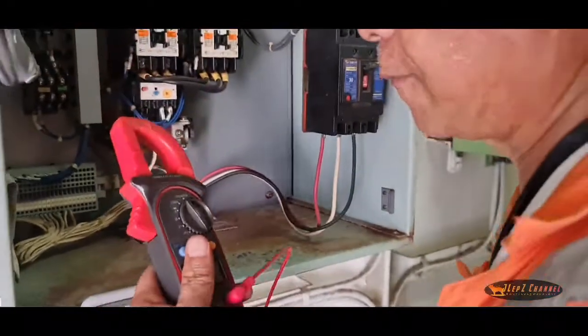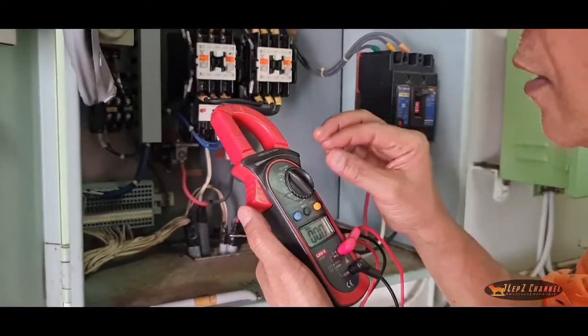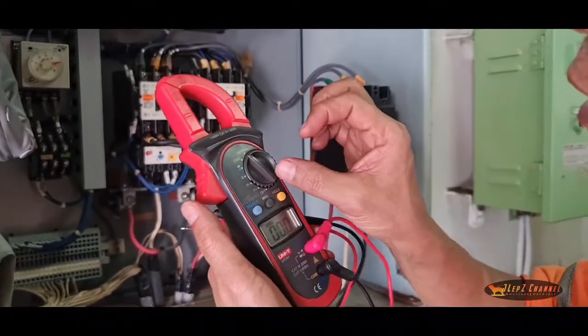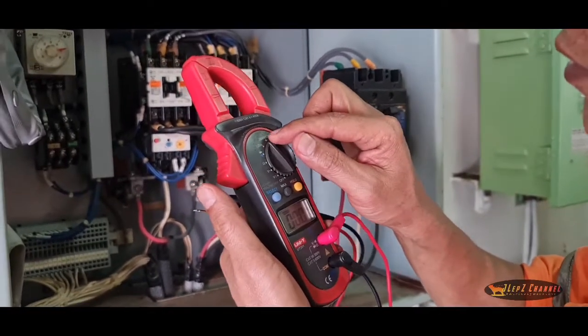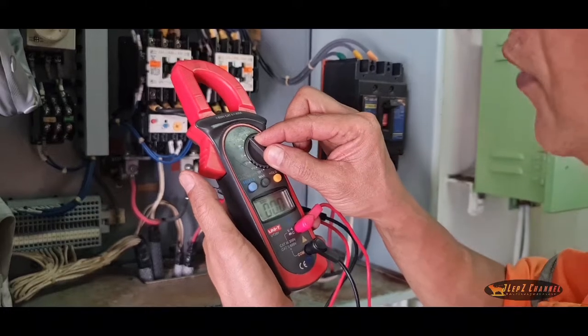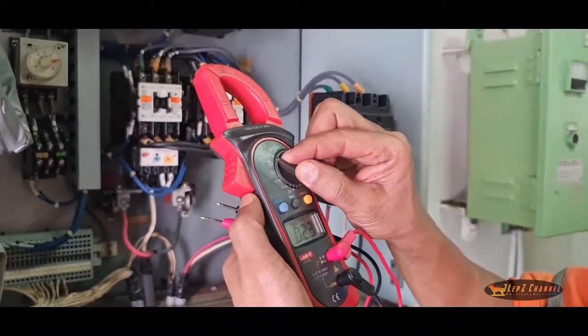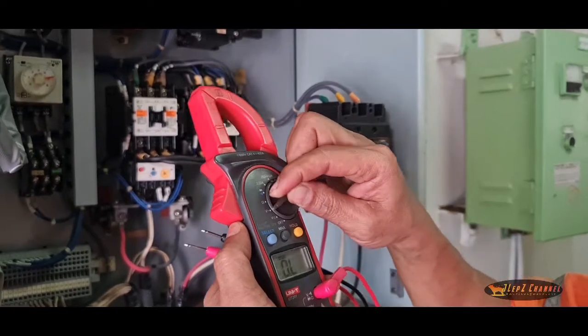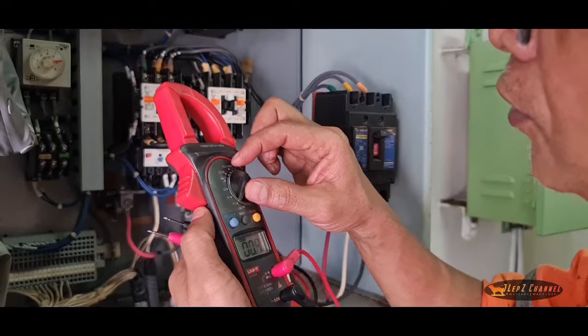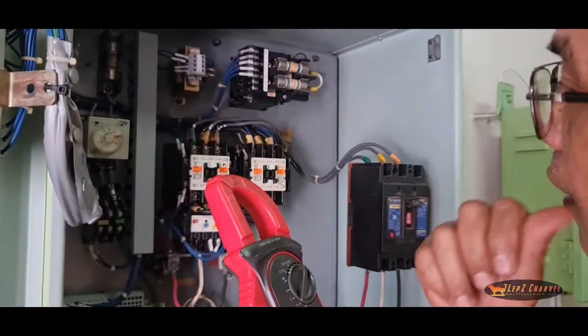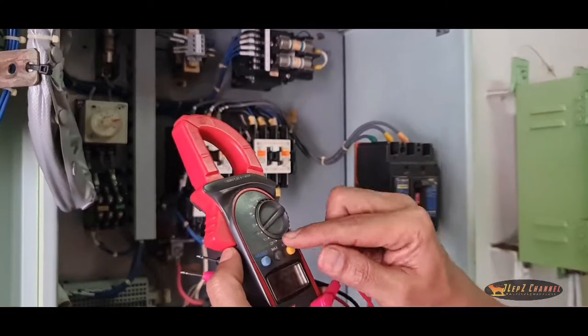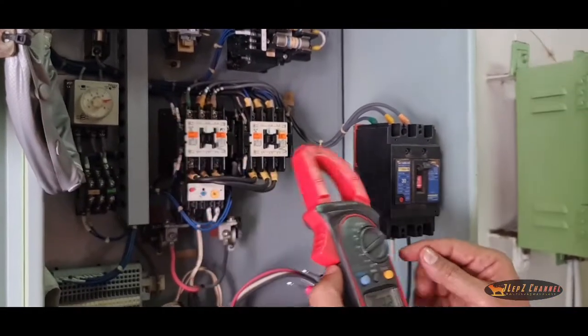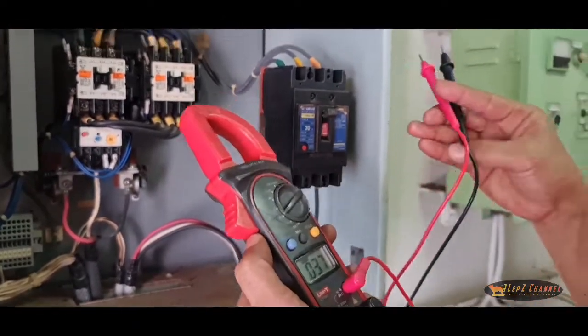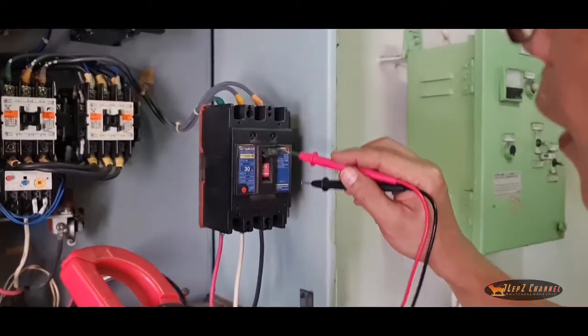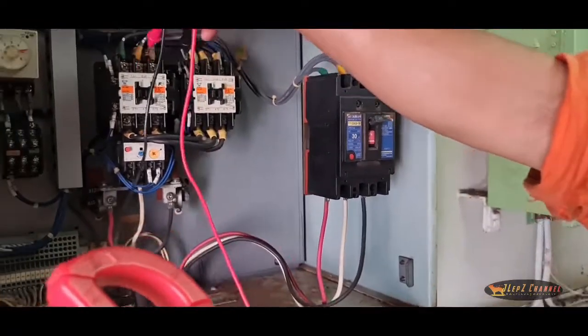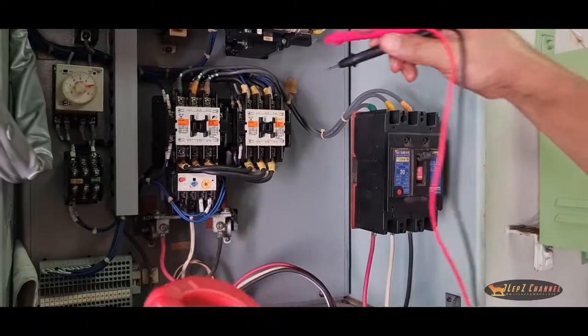Now we will test the voltage. When we test the voltage, do not set the pointer selector to current. Choose voltage, and there are two kinds: one is alternating current and one is direct current. This panel board is using alternating current, so we will also use alternating current voltage. Here, this is the line side of the circuit breaker. This is the load side going to the magnetic contactor.